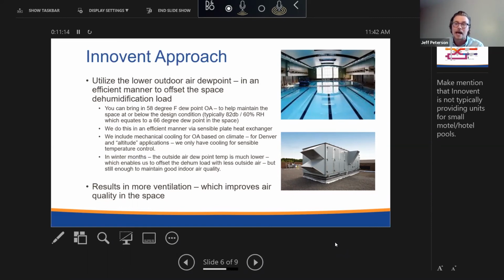So we draw that back actually in the hottest parts of summer to less percentage of outside air, and then we sensible cool it so that what we're providing to the space is comfortable for the occupants. So our unit design is using a sensible aluminum plate heat exchanger to do airside energy recovery. And the two major benefits of that are you've got better indoor air quality because we're bringing in much more than the ASHRAE prescribed minimum, and we're running compressors a lot fewer hours than a mechanical dehumidifier would be.